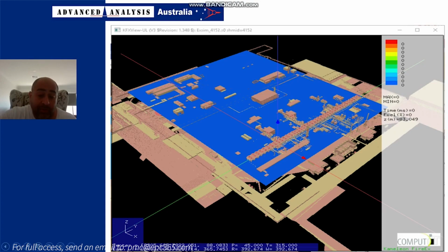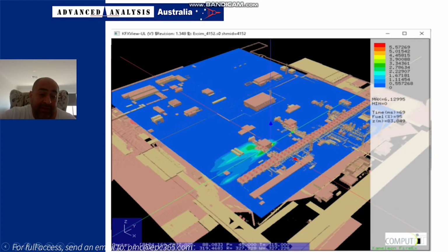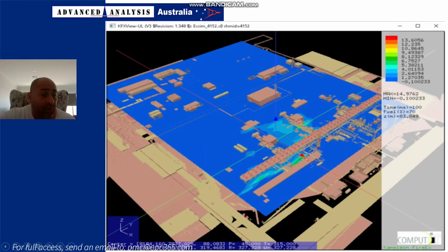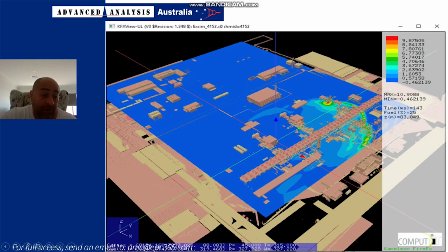Let's talk about gas explosions. In the past, to do a gas explosion using CFD, you basically had to model the site in 3 dimensions. That's expensive, it's time-consuming, it may not always be possible, and in fact, the end result of 3D CFD used for explosions has a large uncertainty.